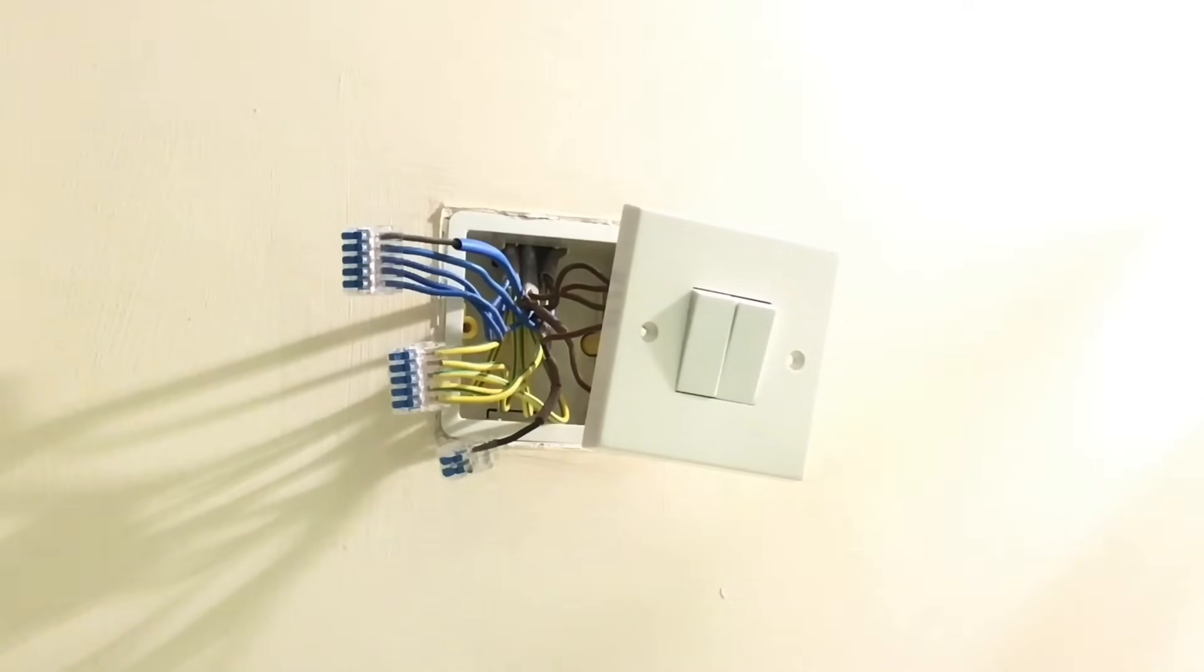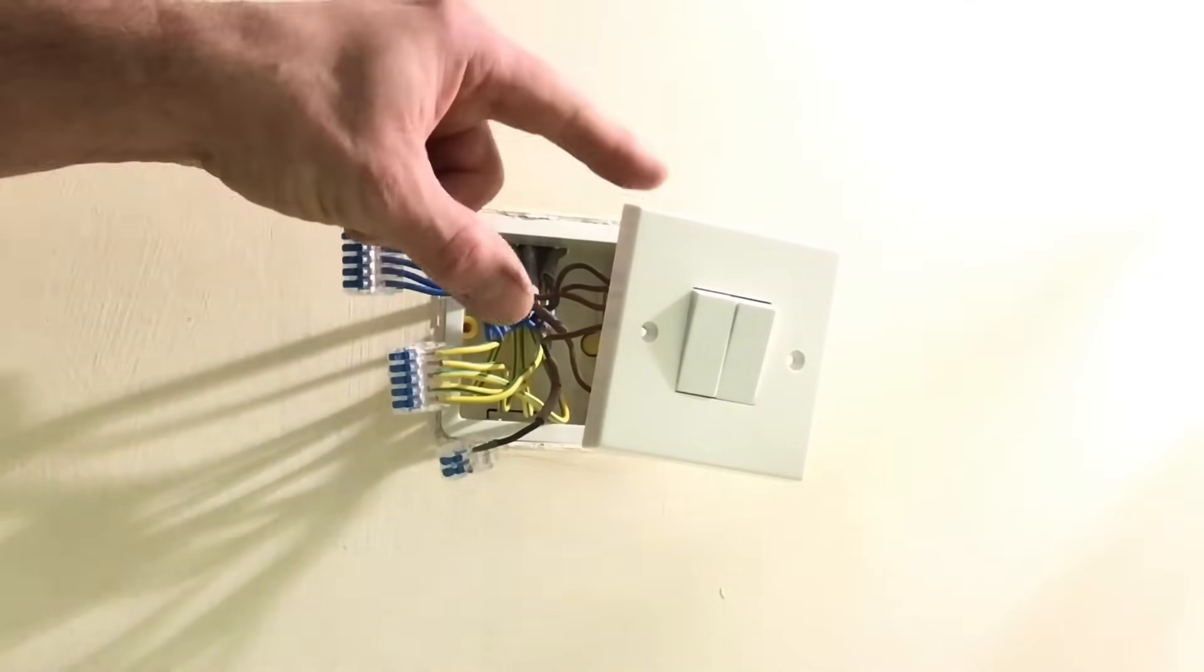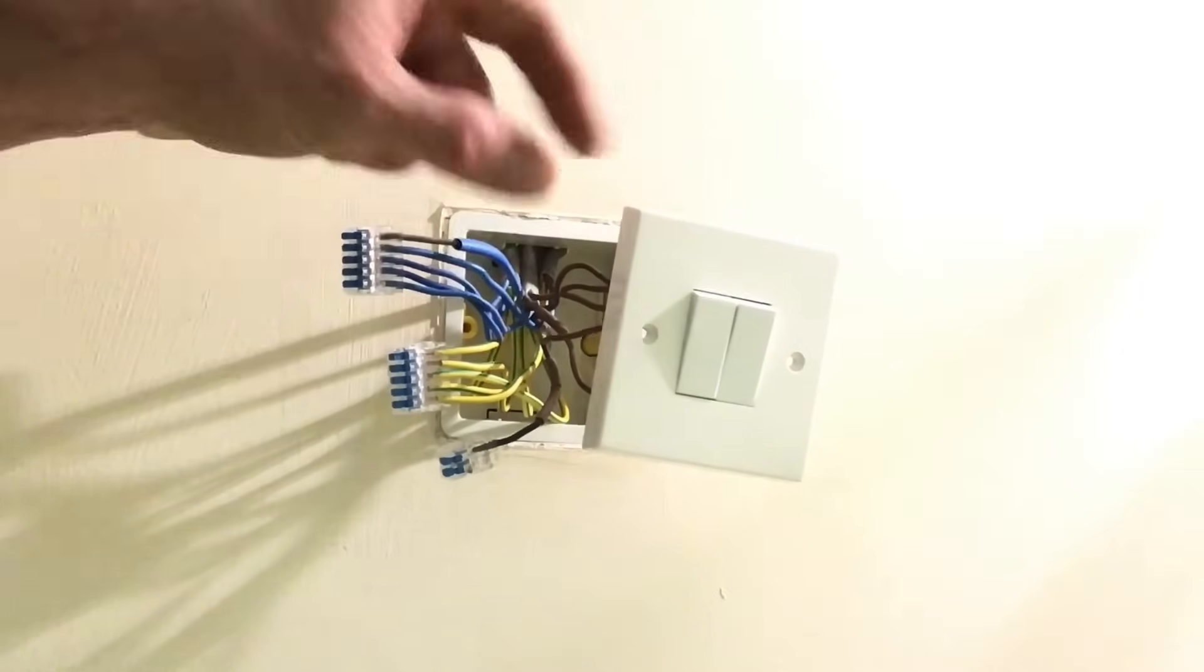However, there is also a feed coming out of here, going to feed a 5 amp socket outlet and plug top for a TV. And they've used a 3 core, which I would suggest was probably two-waying the main lights in the room. They've actually taken that 3 core out and used it as a feed to feed the other switch and then changed that switch to a one way outside lighting switch.